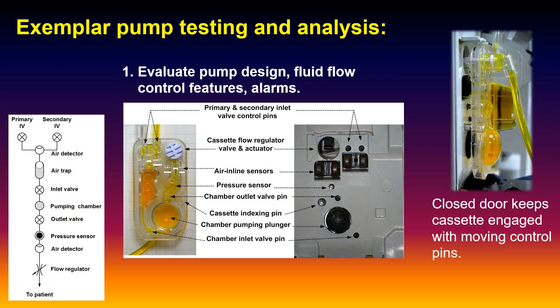So this is just some colored fluid. I had water in the cassette to show the relative location. That cassette has to have very, very firm contact with the pump body. There are these little solenoid valve plungers and valves that control the flow through the cassette.